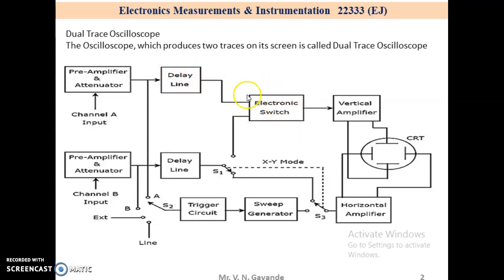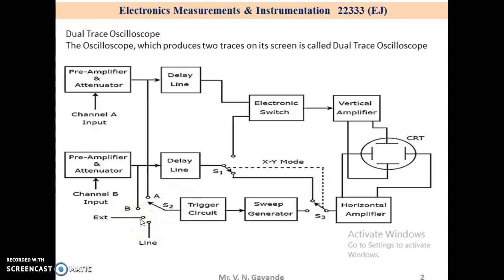With the help of an electronic switch, we can connect the delay line output of a specific channel A or B to the vertical amplifier. We can choose any one of four signals as a trigger input to the trigger circuit using switch S2. Those signals are: input signal A channel, B channel, external, or line input.